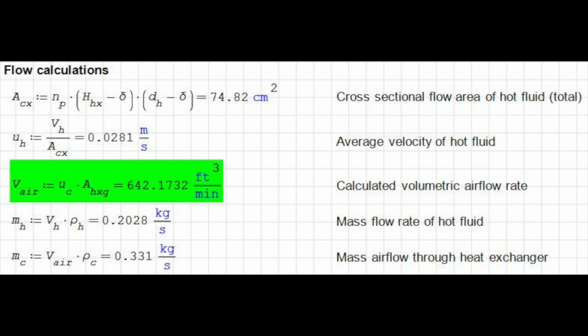Okay, next is flow calculations. We're going to look at the cross-sectional flow area of the hot fluid, right? So pretty much length times width times the number of plates. That gives you your total cross-sectional area for the hot fluid. The average velocity of the hot fluid is the volumetric flow rate divided by the cross-sectional area, of course. So the liquid flow through the heat exchanger at the cross-section of plates is approximately 0.03 meters a second. The calculated volumetric airflow rate is here. It's the velocity times the cross-sectional area, and that gives you your 642 cubic feet a minute.